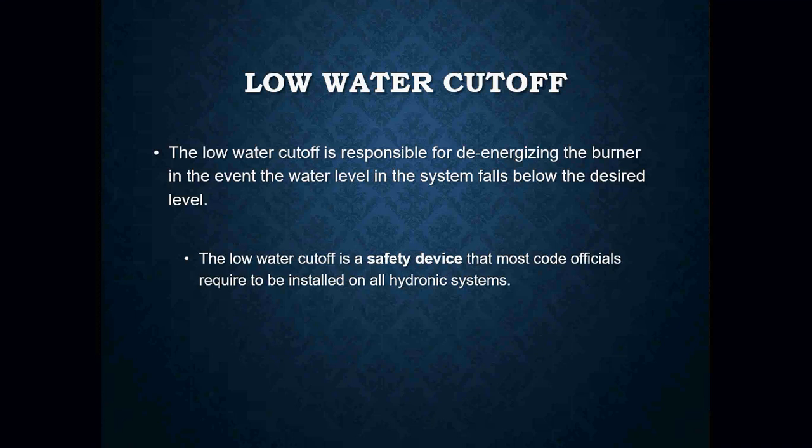If a low water cutoff is open, it is because of a water level situation. Just like the name of the device says — low water — the water level in a boiler has to be at a pre-set point in order for that device to work properly. If it's not sensing the water level, it's not going to operate.